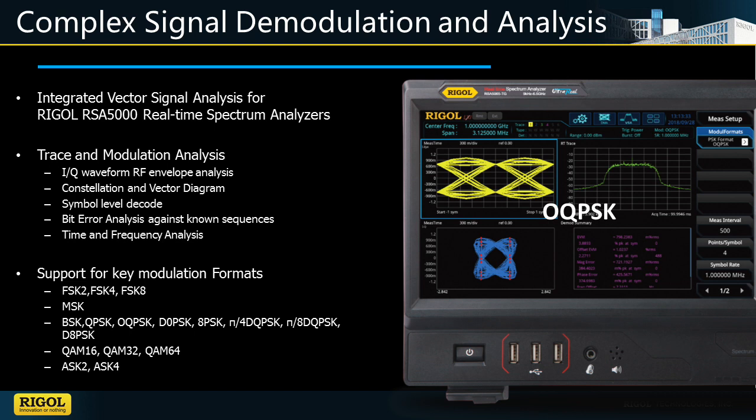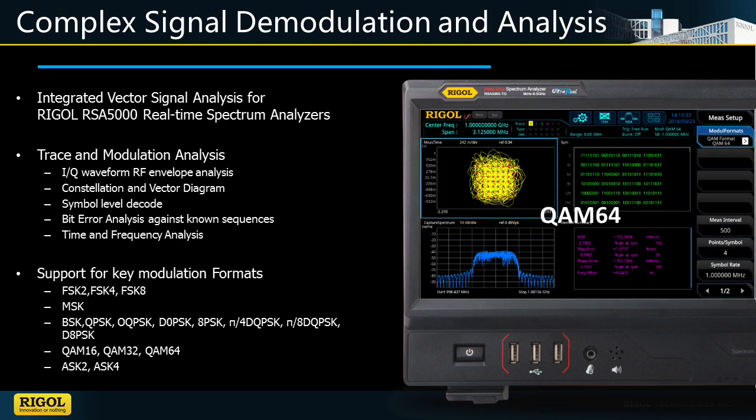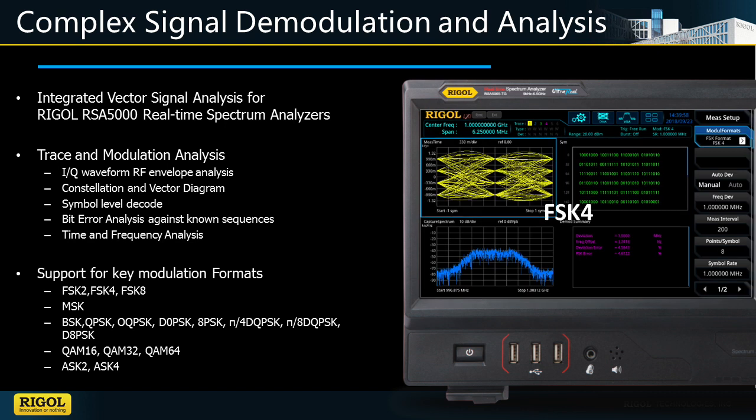The VSA application can be added to an RSA 5000 series real-time spectrum analyzer, with a license code tied to the instrument's serial number. An RSA 5 with up-to-date firmware can add this as one of the instrument modes. Once activated, it can be selected from the mode menu, just like with swept, real-time, or EMI.